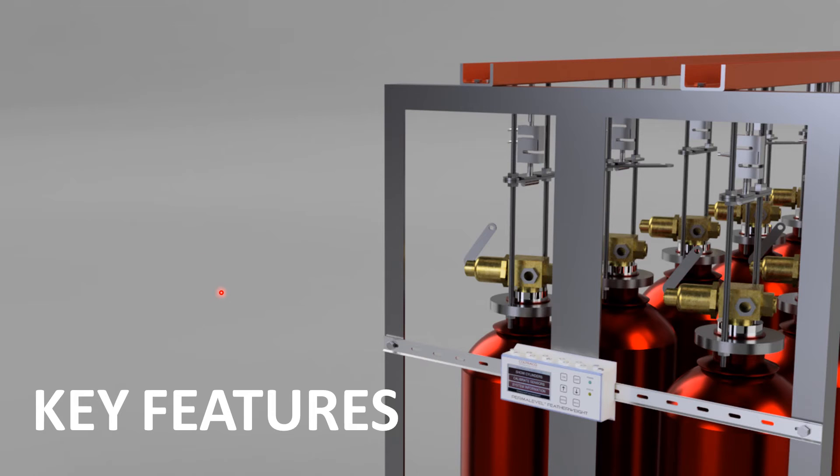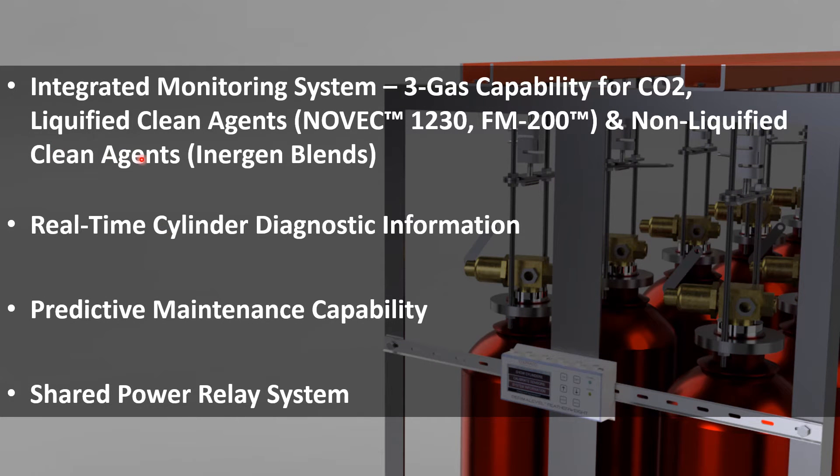Now we're going to go through a few of the key features. It is a fully integrated monitoring system — the world's first dedicated three gas system capability to continually monitor loss of agent quantity due to leakage in high-pressure seamless cylinders containing CO2, liquefied clean agents such as Novec 1230 and FM-200 with nitrogen, and non-liquefied clean agents such as Inergen. For non-liquefied clean agents where pressure is used as a direct indication of agent quantity, our system converts the cylinder's fill pressure to agent mass. Therefore, the user does not have to worry about temperature fluctuations during maintenance schedules, because agent mass is independent of temperature, with the ability to set pressure equivalent leak alarm thresholds, allowing you to adhere to ISO and NFPA regulatory requirements more easily.